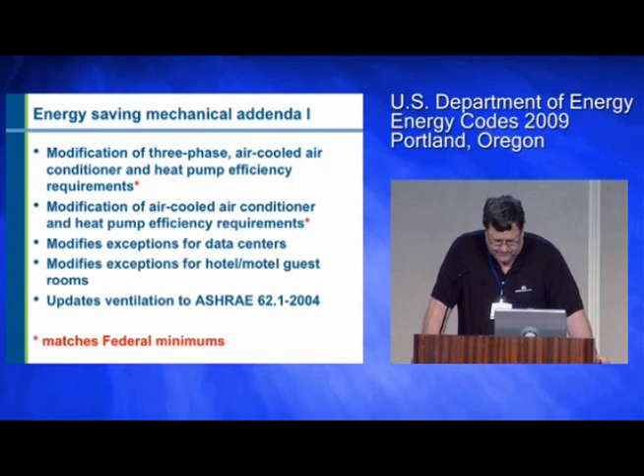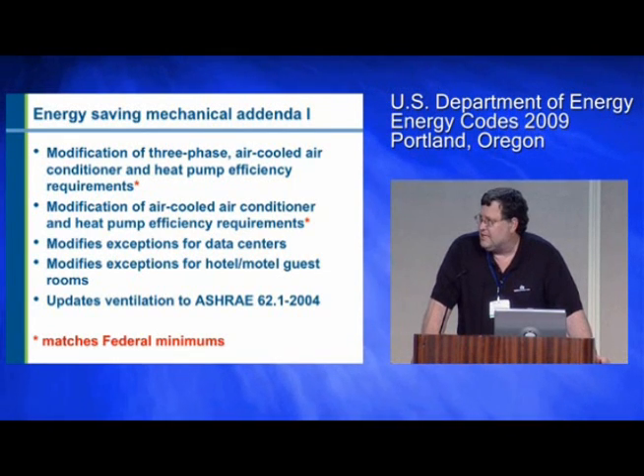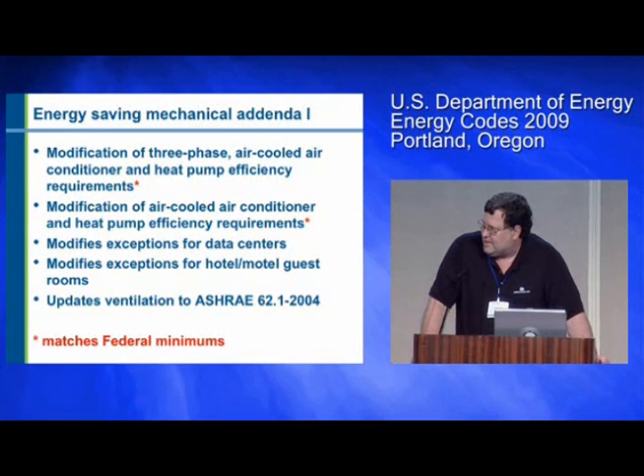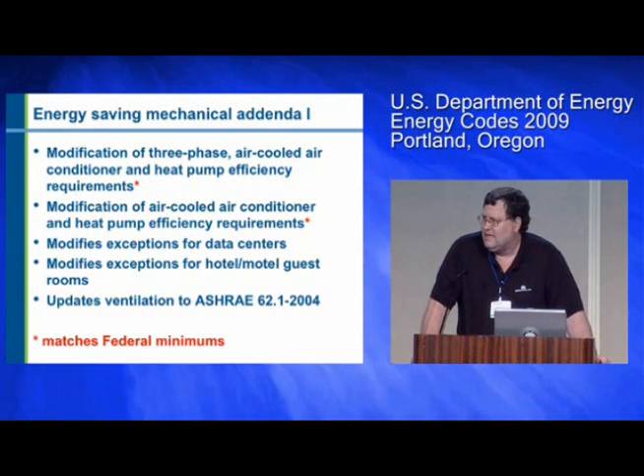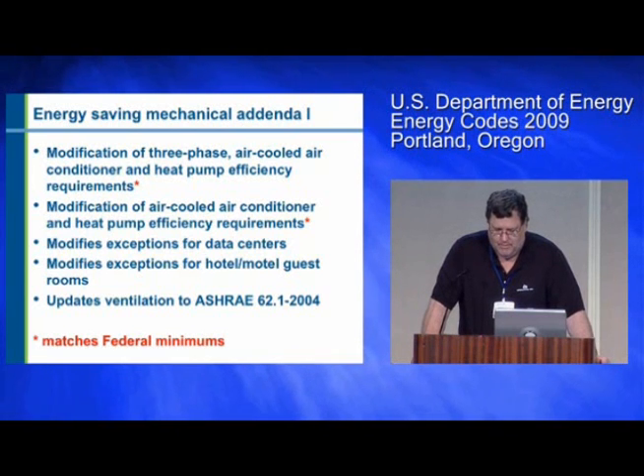On the mechanical side, we've got a whole bunch of changes. Some of the changes that are in standard 90.1 2007 are merely changes that are updating the requirements that are printed in the standard to minimum federal manufacturing standards. There's a change in the standard, but it's really not going to impact too many people because you can't buy equipment that's worse than those numbers anyway. So that's the three-phase air-cooled air conditioner and heat pump efficiency requirements and the air-cooled air conditioner and heat pump efficiency requirements. Both of those were changed in the standard to meet federal manufacturing requirements.